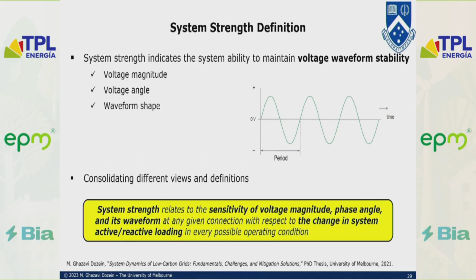If we consolidate all the views presented by CIGRE, IEEE, National Grid, AEMO, AEMC, and others, we can say this is the definition of system strength: the sensitivity of voltage magnitude, angle, and waveform to the active and reactive power changes in your system. So what would happen to the voltages? If voltage is very sensitive, the system is weak. If voltage is not very sensitive, the system is strong.